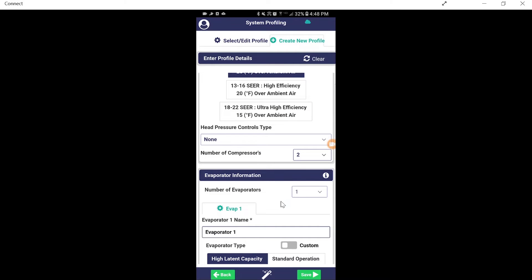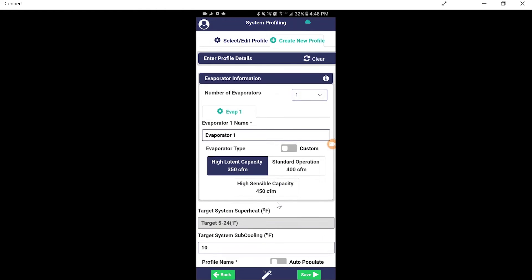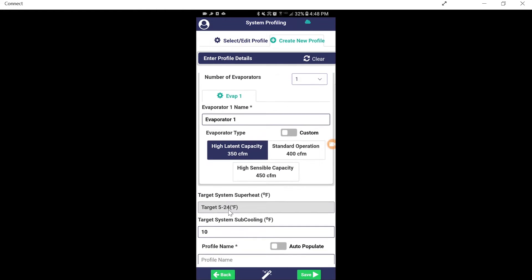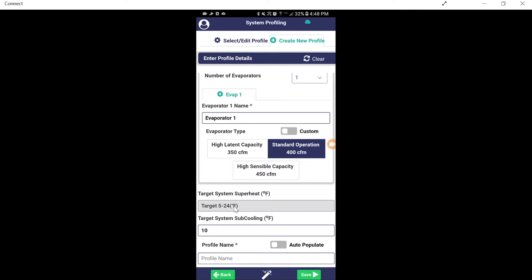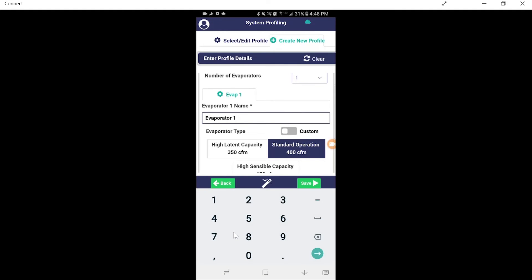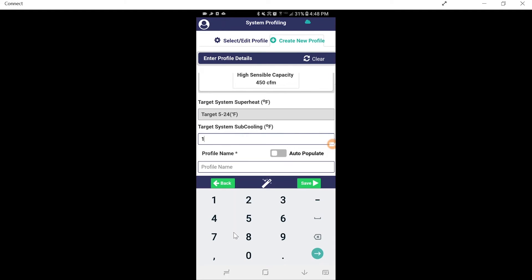We have one evaporator. Standard operation on the evaporator. As you can see, we still offer our target system superheat, which is calculated through the TXV. Target system subcooling, we can always manipulate that. And we're going to change this to an eight.